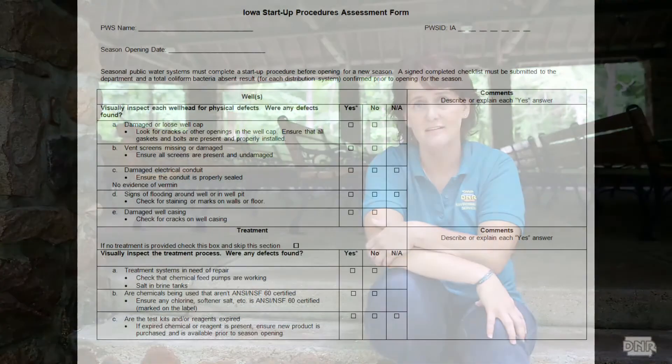The last noteworthy change the rule deals with involves seasonal supplies — water systems that are not open or serving the public year-round. Any seasonal system is now required to collect a bacteria sample each month during their operating season. In addition, seasonal systems must conduct startup procedures each year prior to opening. This procedure consists of completing a checklist and visually inspecting the well, treatment if applicable, and your water storage units. Just like the level 1 assessment, this checklist is helpful and easy to perform, but I'll walk you through it in a separate video.